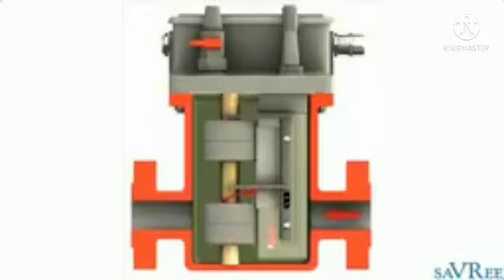If we have a large electrical fault, we're going to get a sudden increase in pressure and a large pocket of gas. This pocket of gas is going to rotate a paddle, and that is going to shut down our transformer. Those are the two functions of a gas actuated relay: to alarm when we have slowly accumulating pockets of gas that are caused by small electrical faults, and to shut down when we have sudden large increases in pressure and gas that are created by large electrical faults.